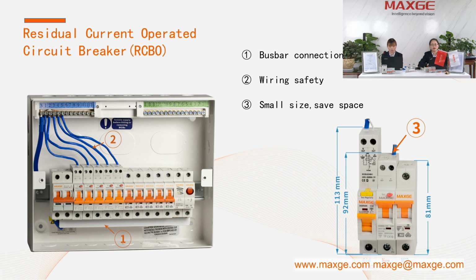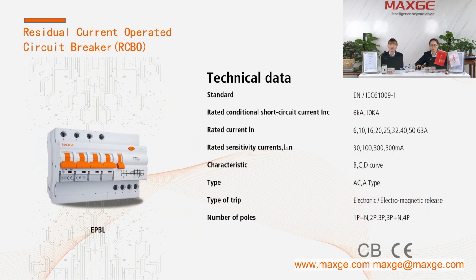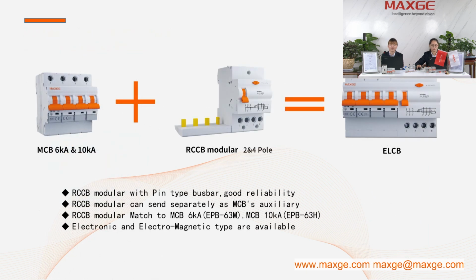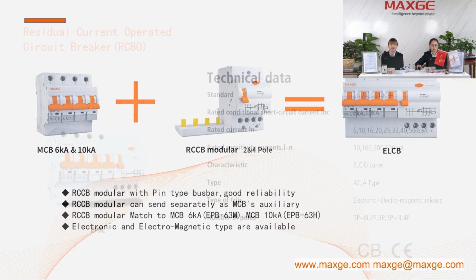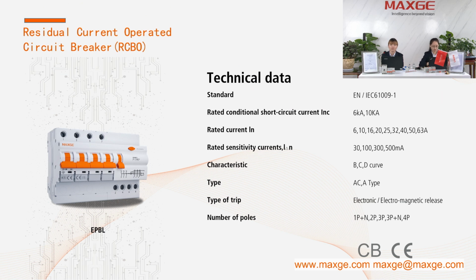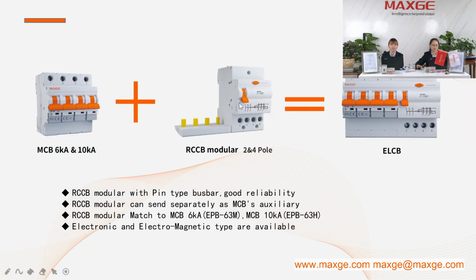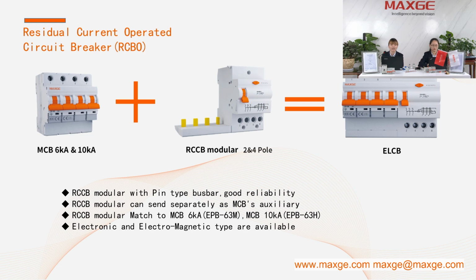We also have ELCB. Here Fiona will give you a simple introduction. Now we are making a new design for MCB with RCCB modular type, named ELCB type RCBO. It is mainly for the domestic market. Rated current is from 6 ampere to 63 ampere with BCD curve. Its rated sensitivity current is 30, 100, 300, 500 mA. It has AC type and A type, and from 2-pole to 4-pole. RCCB modular with pin type busbar, good reliability. RCCB modular can be sent separately as MCB's auxiliary. RCCB modular matches MCB 6kA and 10kA. It has electronic and electromagnetic type.